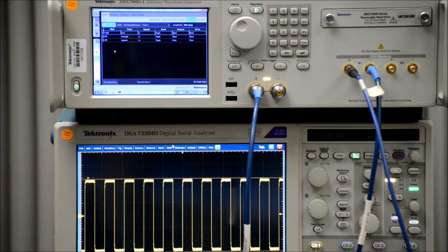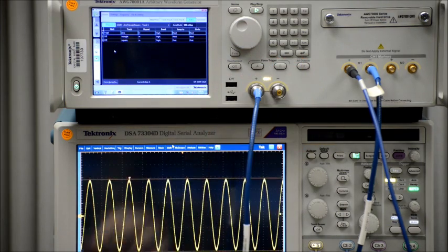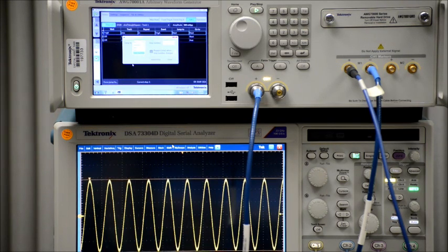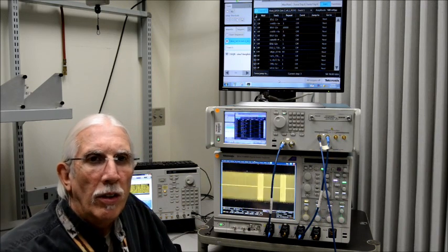Let me go ahead and force a trigger again. It's waiting for a trigger again. We're at the first waveform, so I'll have to hit B to start the waveform. What you can do is a force jump, and you can do it when the number changes, rather than just jumping independently. You can also specify some other criteria in here. So this was just a quick example of what you can do with the sequencer.